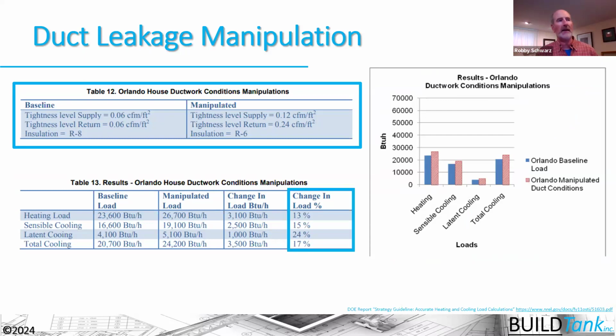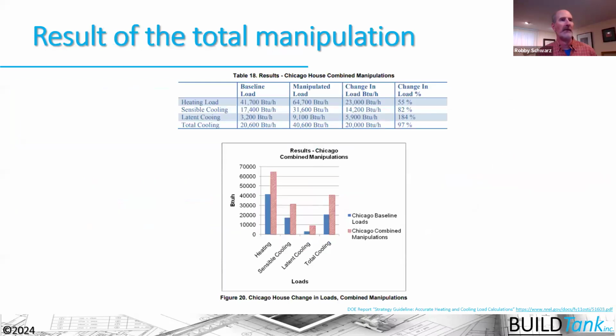And we can see that it can manipulate the loads by 13% or 17%, depending on the numbers that we actually put in to the software there. So this is just kind of the results of all the manipulations there. We can have a heating load that's 55% greater than it needed to be, and we could have a total cooling load that's almost 100% oversized by these manipulations.